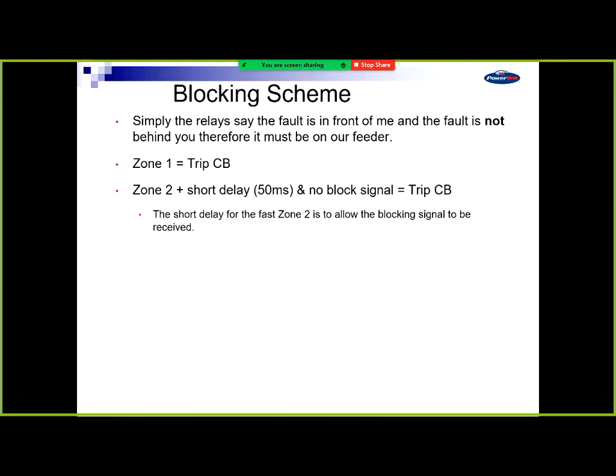A blocking scheme works the exact opposite, basically. We don't have a lot of this in our network now, but it was quite common in the past when we used to use PLC communication, power line carrier. So you were sending communication signals over the physical phase conductor was what was happening, just at a different frequency, but over the phase conductor. If that phase conductor is having a fault at the same time, you've got to send the signal through the fault. Now you can do that, that's not impossible, just increases your probability of not getting through a little bit. So we use a blocking scheme which works in the opposite way. What it works is we have our zone 2 set to go quickly.